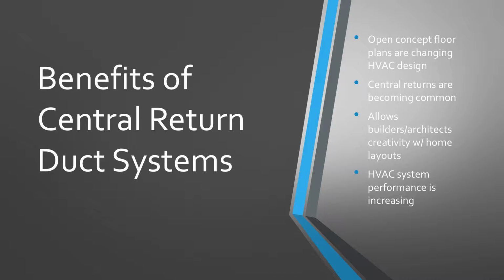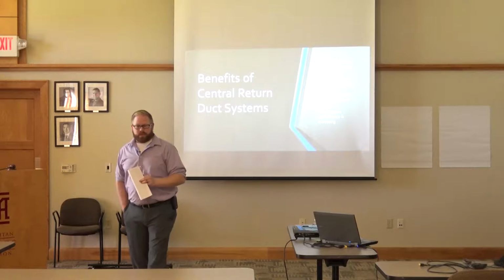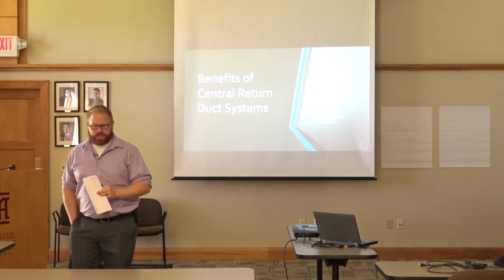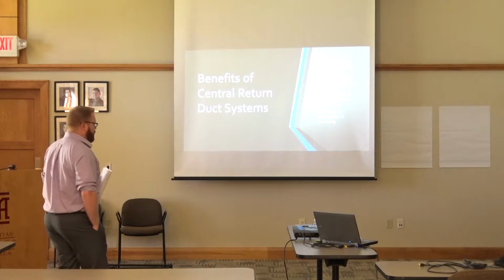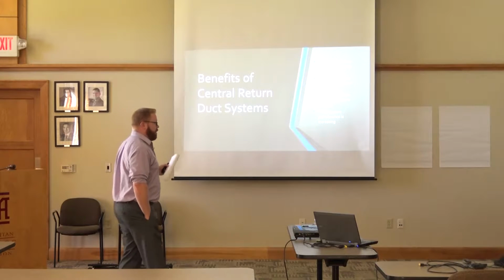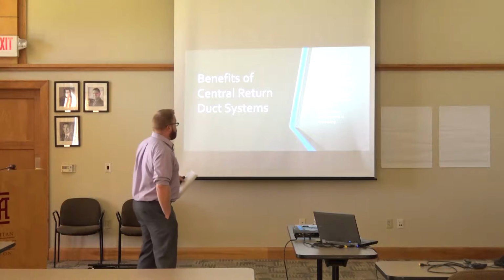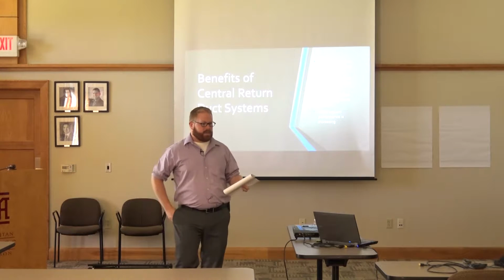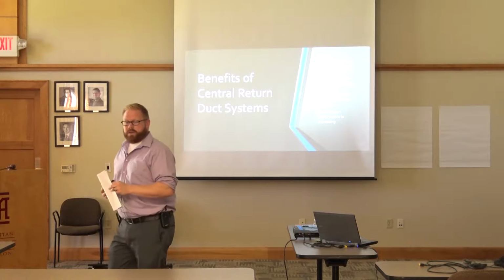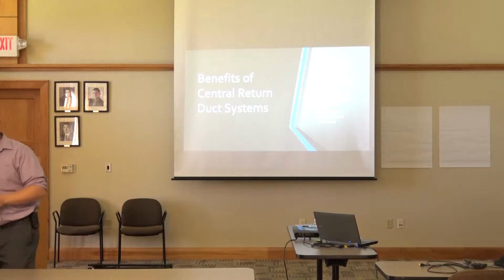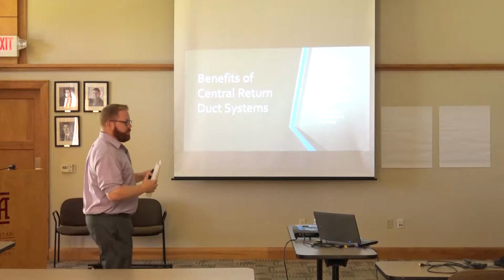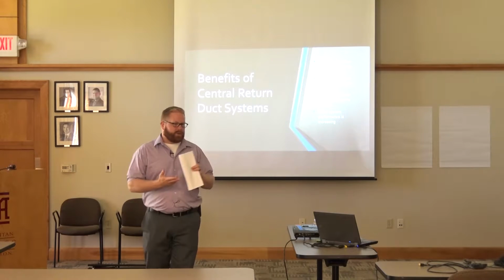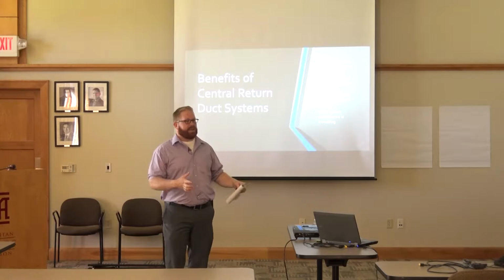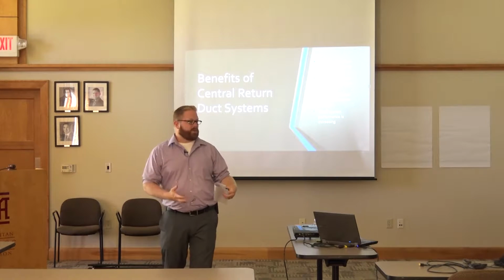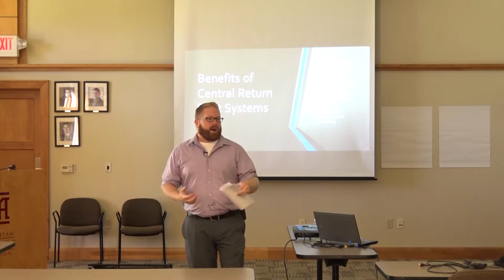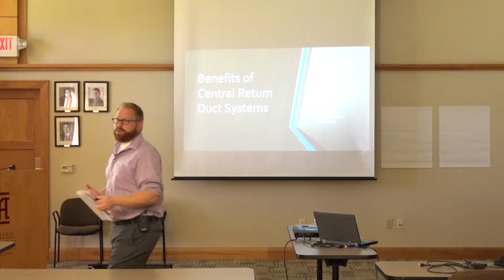Benefits of central return duct systems. With the way the building industry is changing, toward more open floor plans, central return duct systems are becoming more apparent in the industry, mainly due to lack of performance. When an HVAC system is typically installed, we're fighting with plumbing contractors and electricians to try to get enough area for cold air returns, or even supplies, to adequately heat and cool the house.